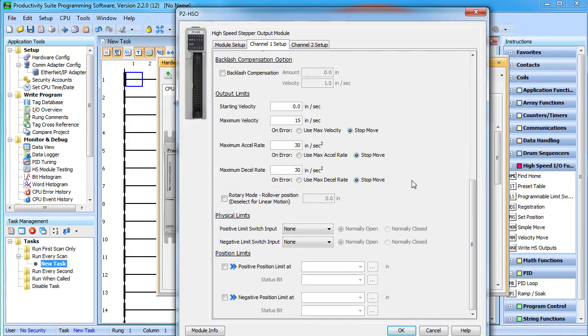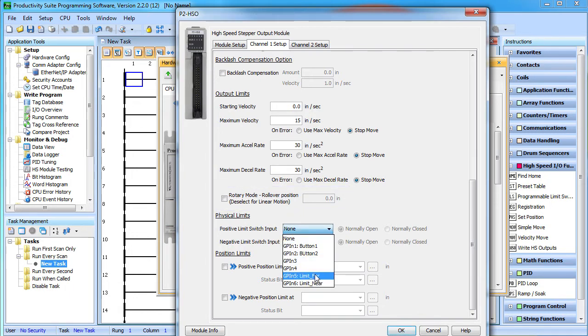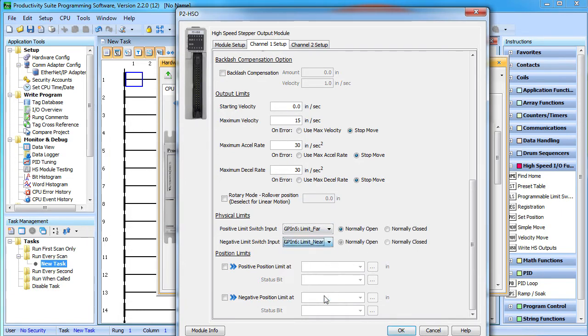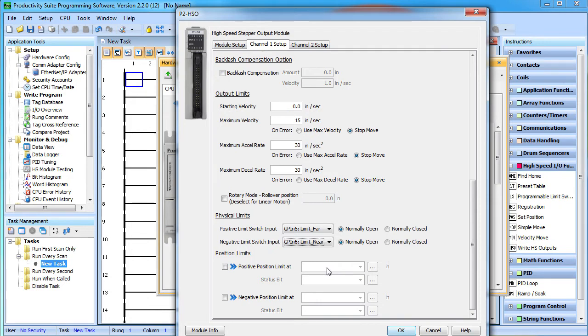We're using proximity sensors on this slide to detect end of travel. And we put those on inputs 5 and 6. Those proximity sensors present themselves as normally open contacts, so I'll leave that set like this. You can also use position limits. We don't really need those because we have the proximity sensors, but I'm going to specify them anyway so we can use them during our demo.